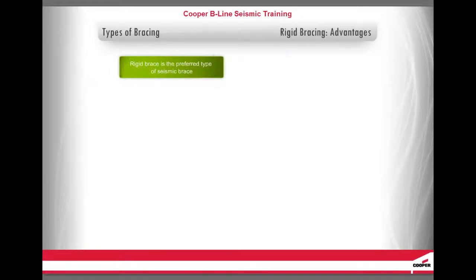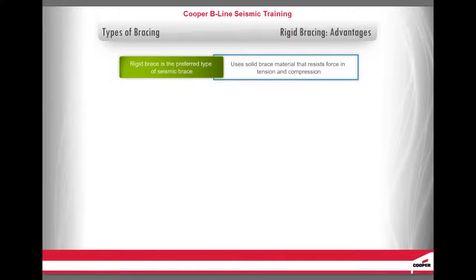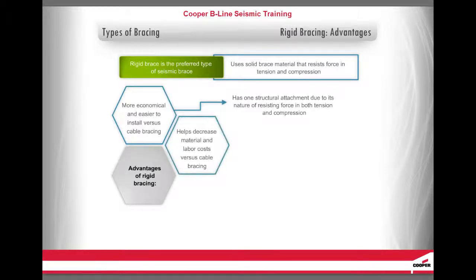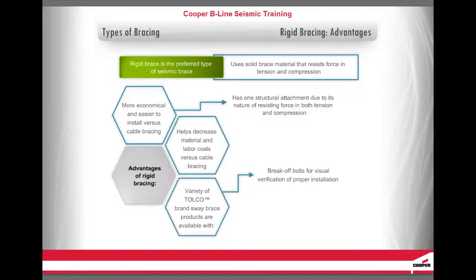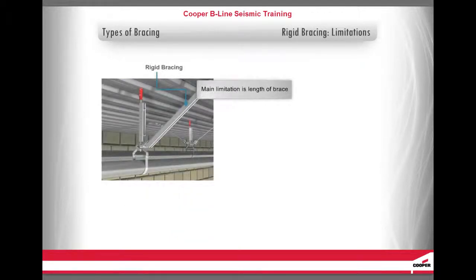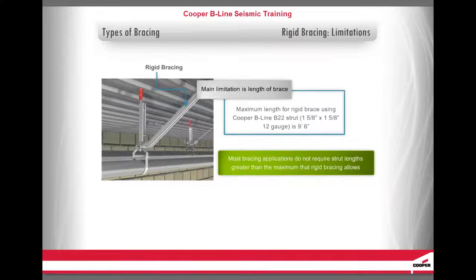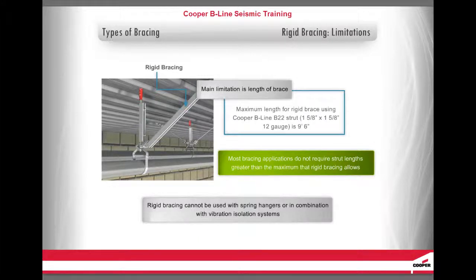A rigid brace is the preferred type of seismic brace. It uses solid brace material that resists force in tension and compression. The advantages include being more economical and easier to install versus cable bracing, requiring only one structural attachment. A variety of Tolco brand sway brace products are available with break-off bolts for visual verification of proper installation torque. The maximum length for a rigid brace using Cooper B-Line B22 strut is 9 feet 6 inches, which covers 95% of bracing applications. Rigid bracing cannot be used in combination with vibration isolation systems.